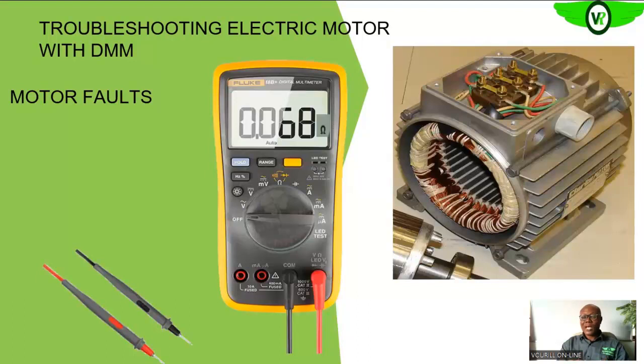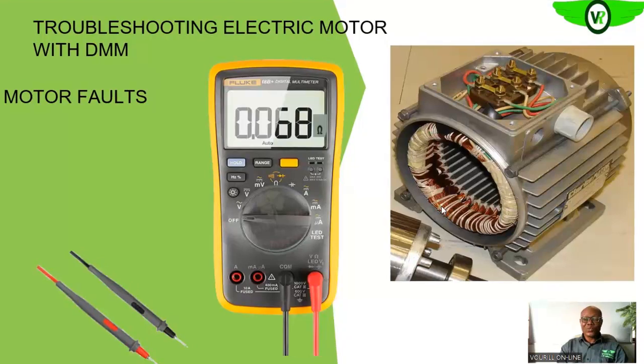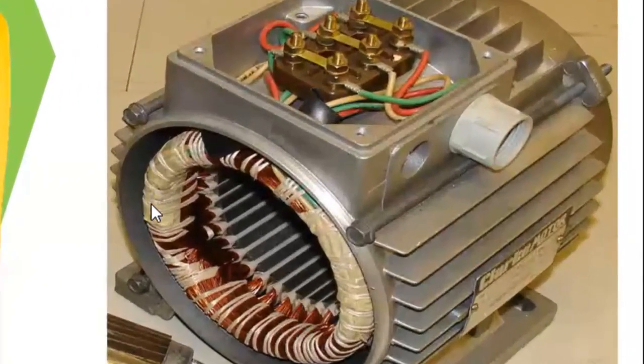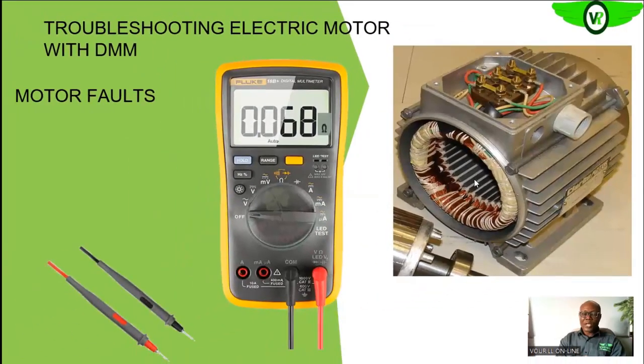Now, we know that the major active components in the electric motor are these windings. And these windings don't have any interaction with one another, each phase winding, except at the point you deliberately make those connections. Then again, the winding does not have any connection or interaction with the yoke, that is the frame of the electric motor.